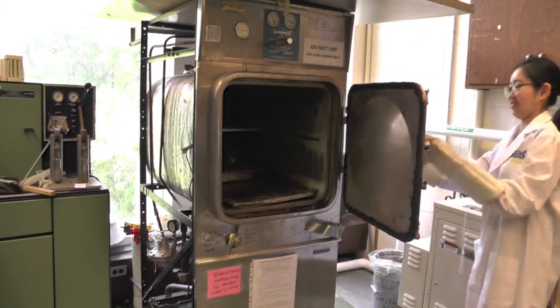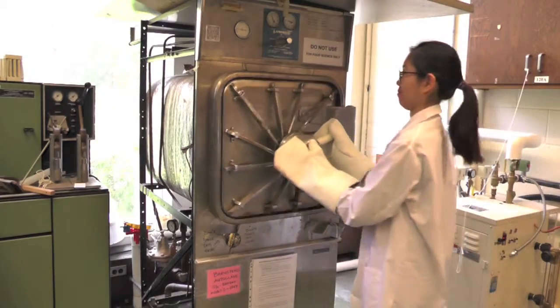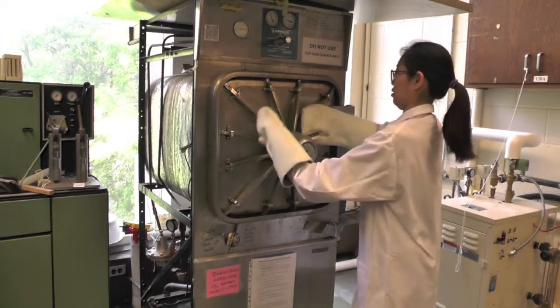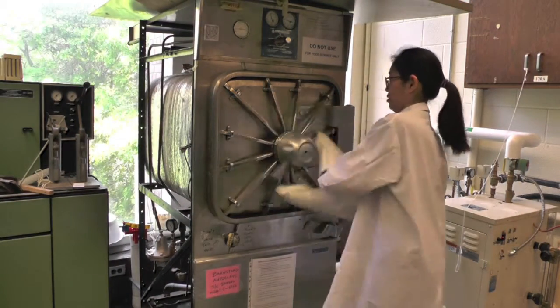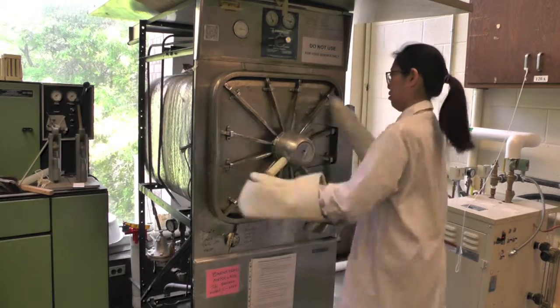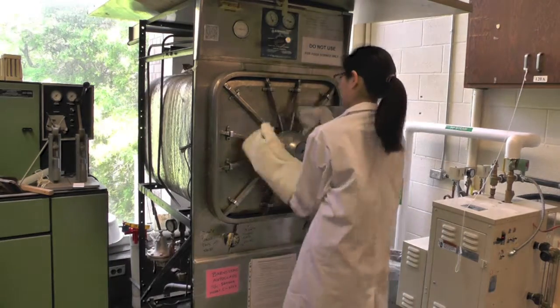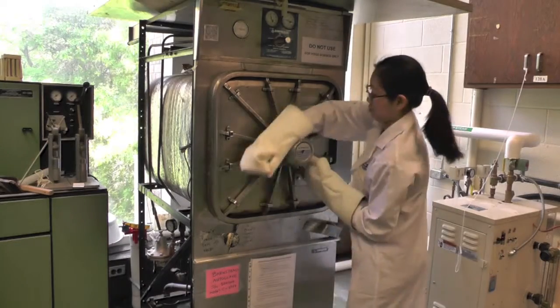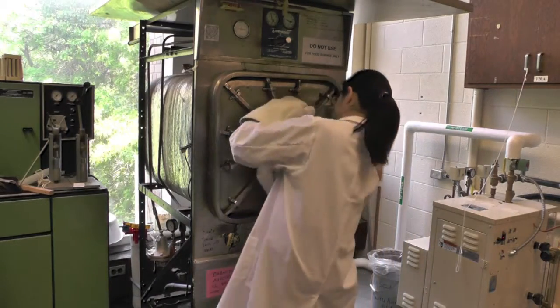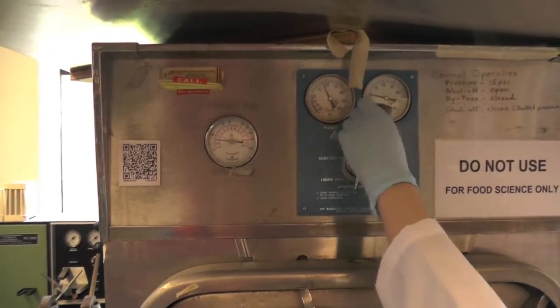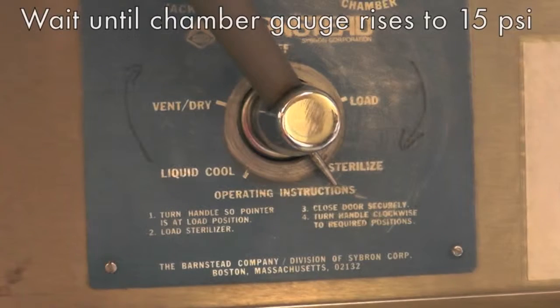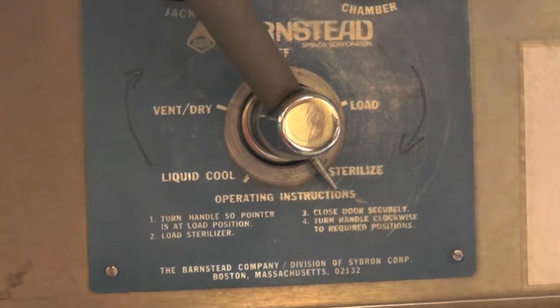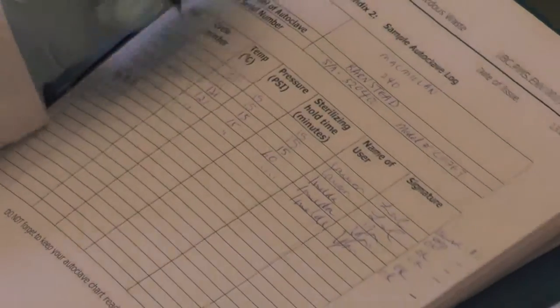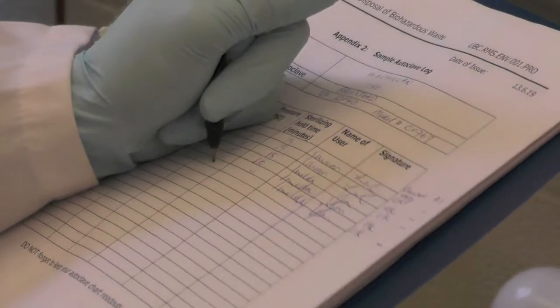Shut the autoclave door by first tightening the inside ring to lock the door. Then screw tightly the outside ring until you can no longer turn the knob clockwise. It is important to close the door as tightly as possible. Once the door is securely closed, turn the knob to sterilized position and the chamber gauge will begin to rise slowly until it reaches 15 psi. In the meantime, record your usage in the autoclave logbook.